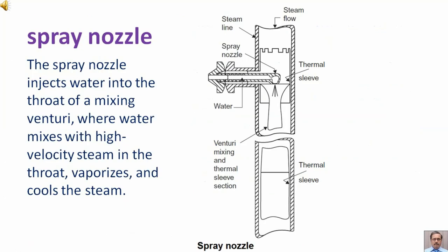The spray nozzle injects water into the throat of a mixing venturi, where water mixes with high velocity steam in the throat, vaporizes and cools the steam.